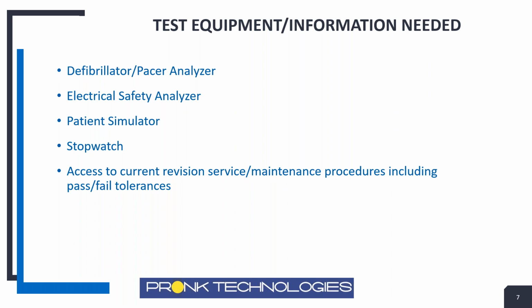And the manuals are written in such a way where the manufacturer is trying to account for the wear and tear, the things that can go wrong with the device, and wanting to give us as technicians that information so we're looking out for these things when we're doing the service. So having that service maintenance procedure, that PM procedure, is really critical. Not only the procedure, but of course also knowing what are the pass-fail tolerances. We also want to make sure we document all these results. As we mentioned, we want to keep track of these critical devices and everything we did so that we're confident we completed all the steps and we have that confidence that this device is really ready to go back onto the clinical floor to be used on patients.